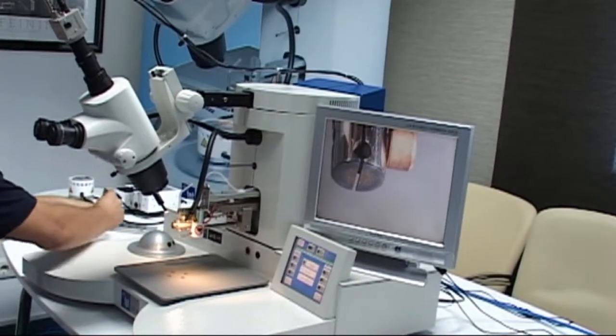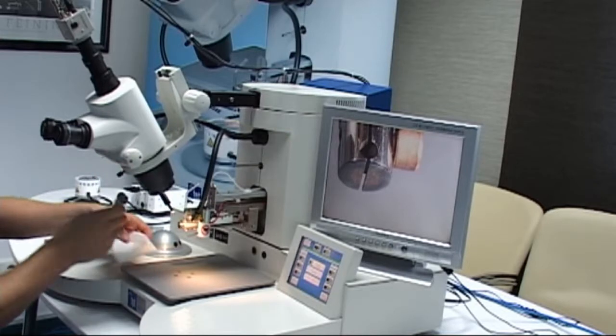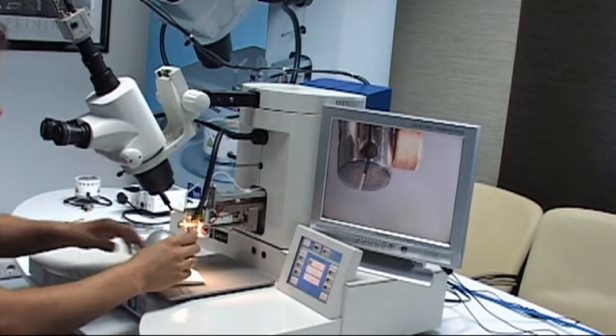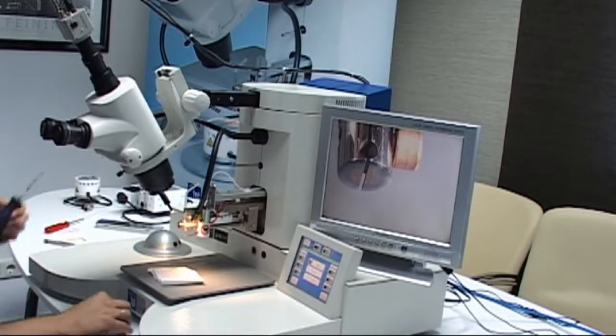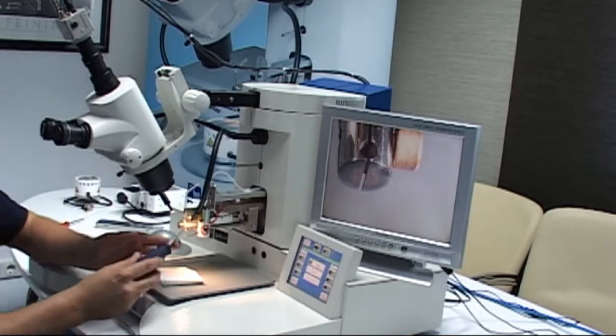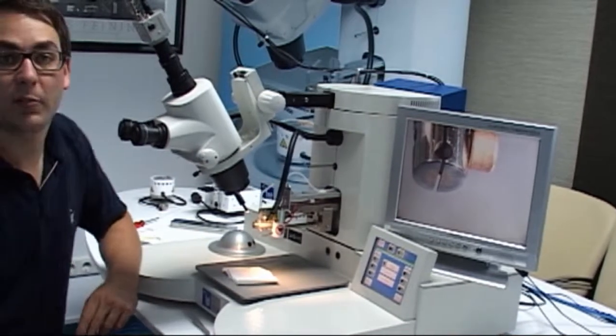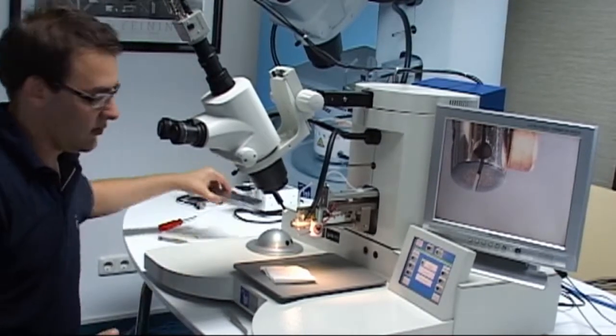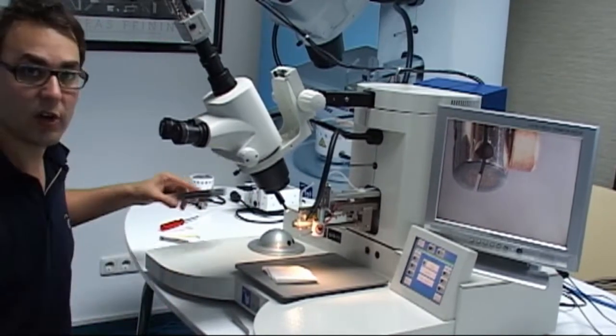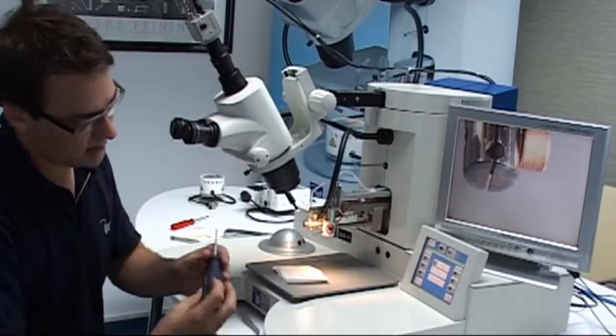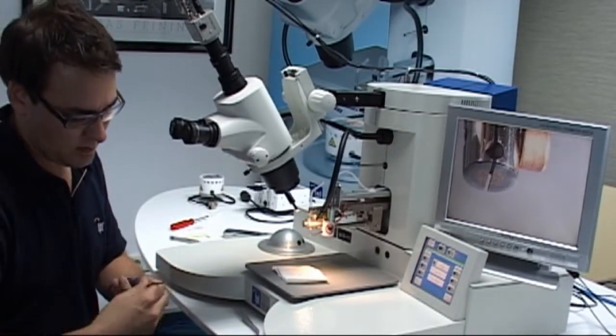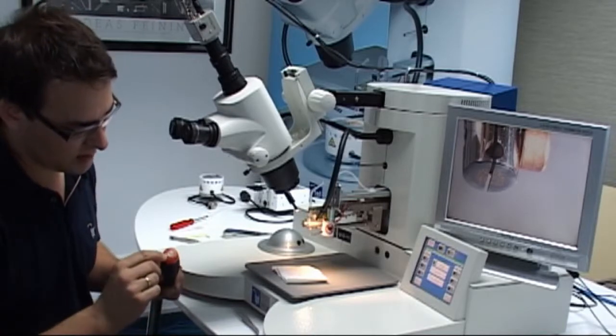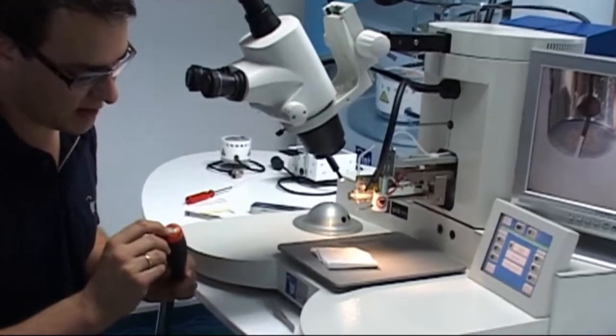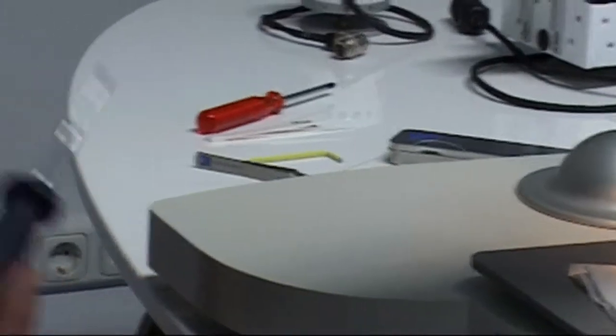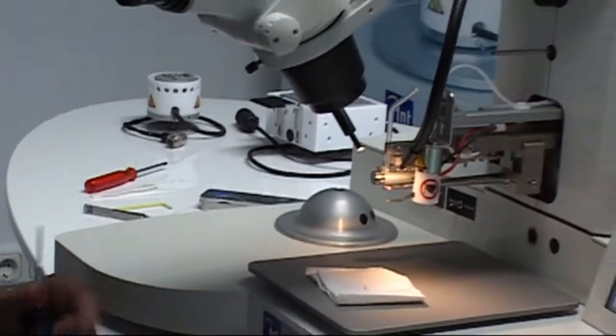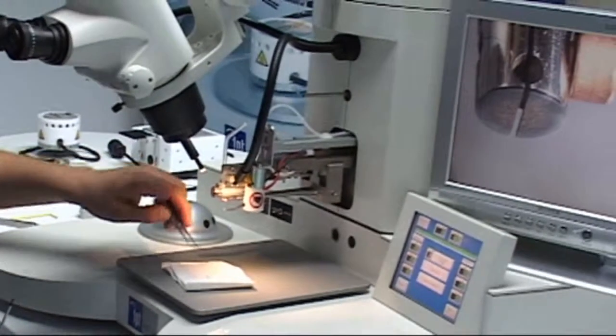So we install the tool. I've taken out the tool, I put it here on some paper tissue. Usually when you receive your bonder, the transducer screw will not be installed, so you will find it in this box. You take out the copper screw and install it with this one. You can click on the button and you can see there's 35 centinewton meter. That's the value we adjust the tool. We tighten the tool with this value.